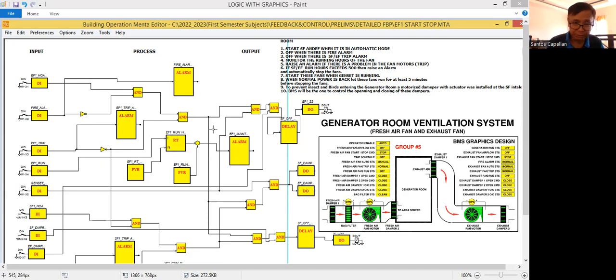Okay, so again, as I said, I have to include the points in the graphics. Now why do you need to include them? Because if you are going to present these graphics, by the way guys, when you are doing the testing and commissioning, you will be presenting the graphics to the consultant. You are not going to show your control logic program. The consultant doesn't care about your control logic program. All he needs to do is check the real-time values being represented by these graphics.